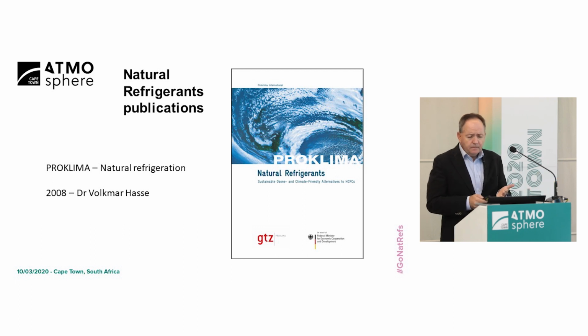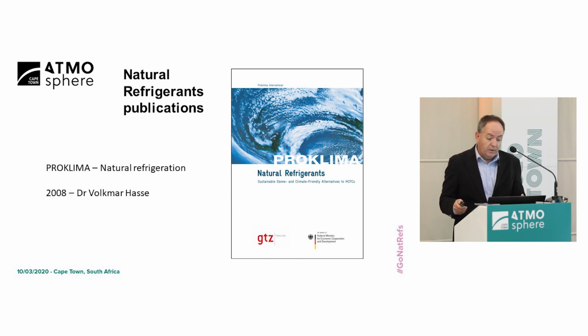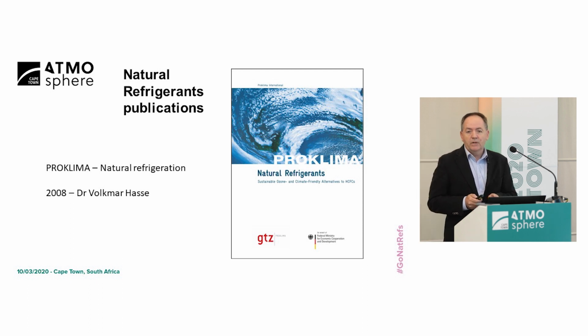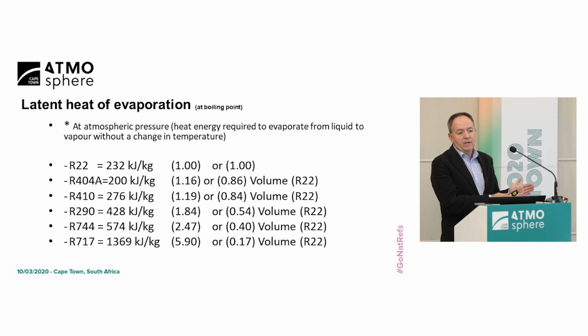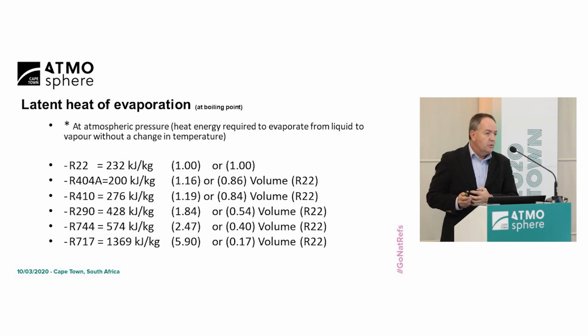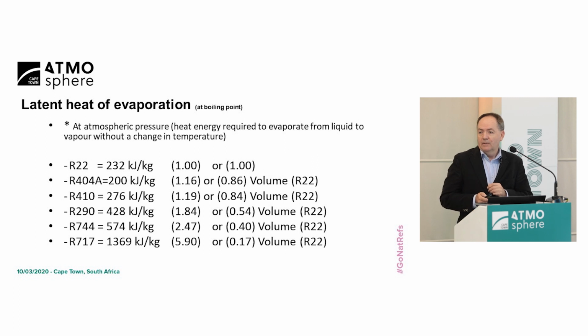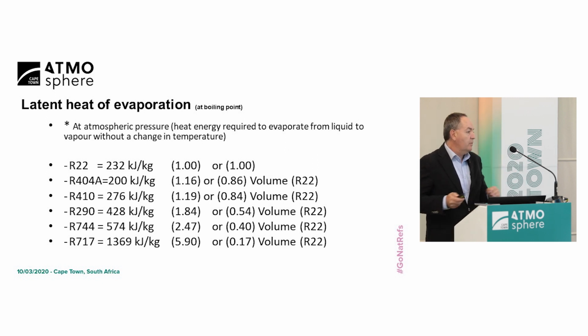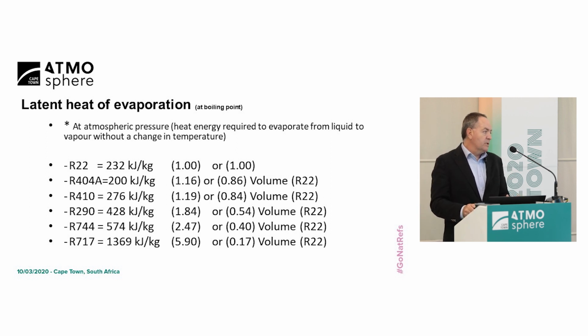So you've heard ammonia, the only refrigerant here with 0 global warming potential and 0 ozone depleting potential. The only one that we're aware of. So I think one thing that makes ammonia very energy efficient is the latent heat of vaporization. If you take a kilogram of high pressure liquid that changes phase and absorbs heat to vapor, and you compare it with R22 as a reference, now 404 does a little bit better, 16% better in theory, 410. Then you get quite a jump. R290 is significantly better. Hey, CO2, no, I think we're in the right place today, but of course ammonia is way better than the rest of it. No?